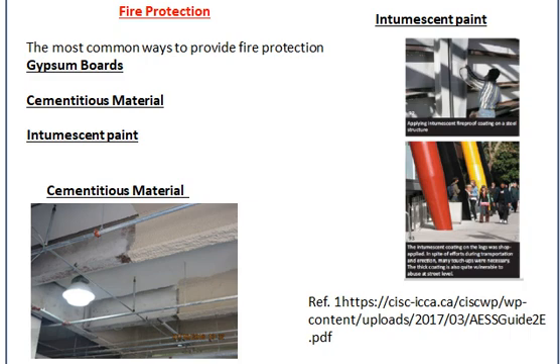Gypsum boards are used when we have a residential building or office building. In these buildings there are partitions and ceilings, and you can utilize gypsum board around the steel structure or steel members to provide fire protection. The thickness of the gypsum board around these members will determine the fire rating or fire resistance of the structure.